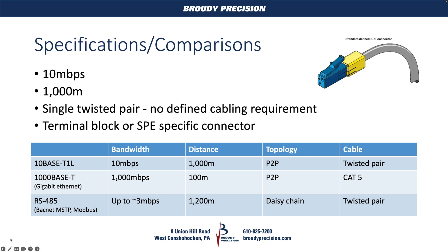You can see that the major difference between RS-485 and T1L is that instead of using a daisy chain like we're used to, we're doing our typical point-to-point connections like we do with regular Ethernet. What that means is instead of having a single terminal block where you're leaving and entering wires on your controller, you'll have two terminal blocks — like we do with Ethernet, one and two — where one side comes in and the other side goes out. Most cases, I think we're going to see controllers that have both of those.